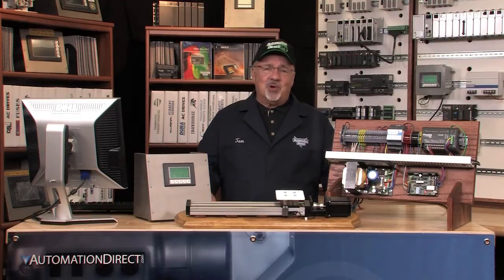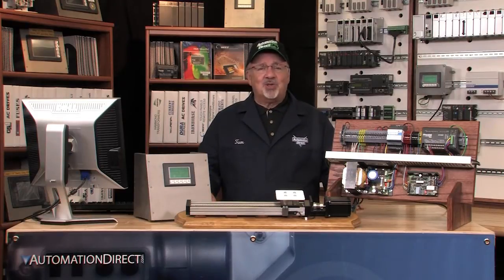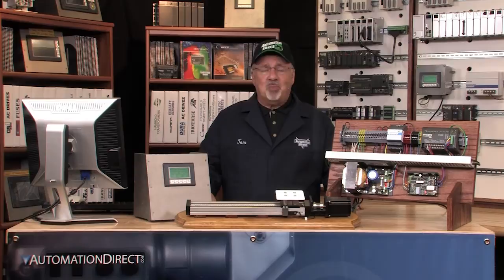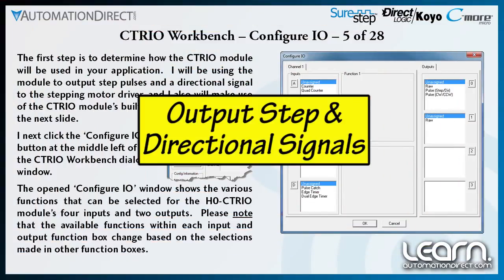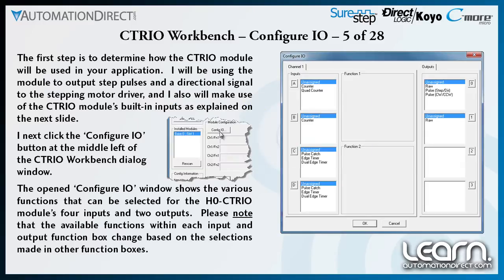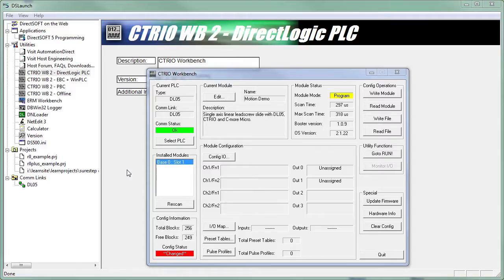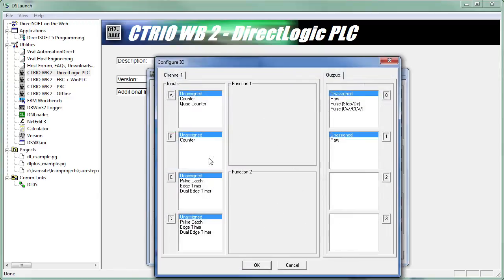Next, I determine how I will use the CTRIO module so that I can configure the module's inputs and outputs. I will be using the module to output step pulses and a directional signal to my stepper motor drive. I click the Configure I/O button at the middle left of the CTRIO Workbench dialog window. The Configure I/O window shows the various functions that can be selected for the H0-CTRIO module's four inputs and two outputs.